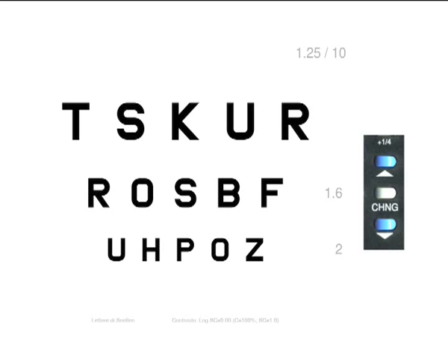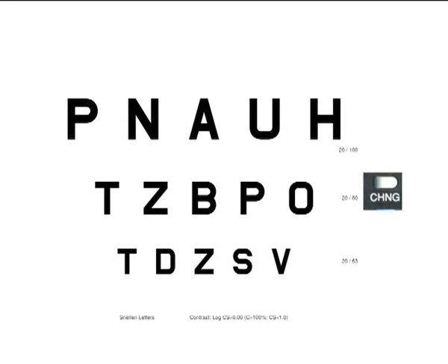All eye chart tests have the same functions. The up and down keys allow to increase or decrease the visual acuity value. The change key allows to choose in a pseudo-random way other stimuli to display.